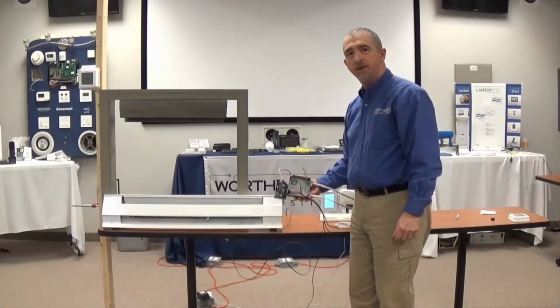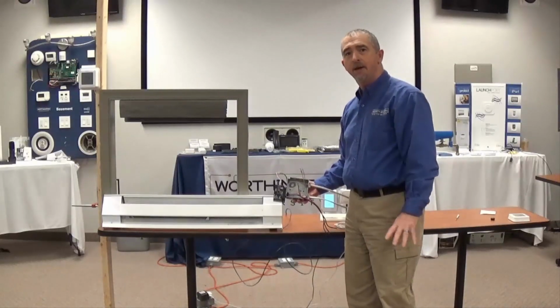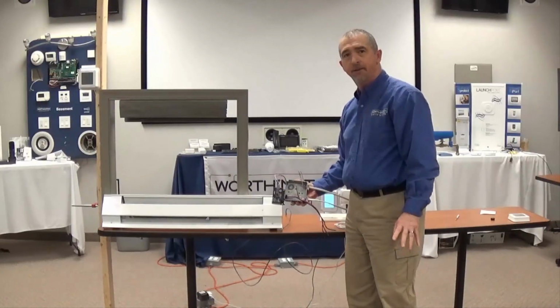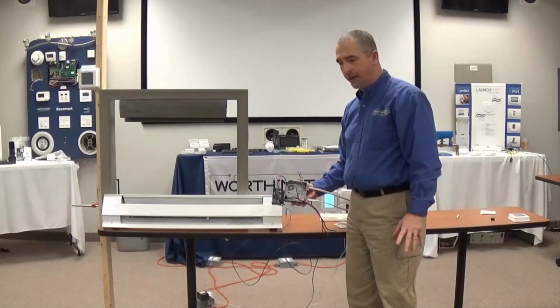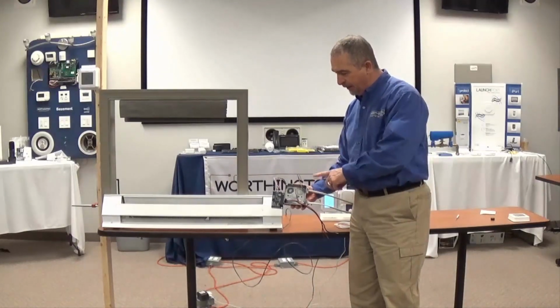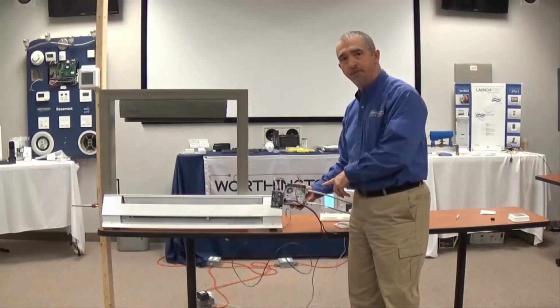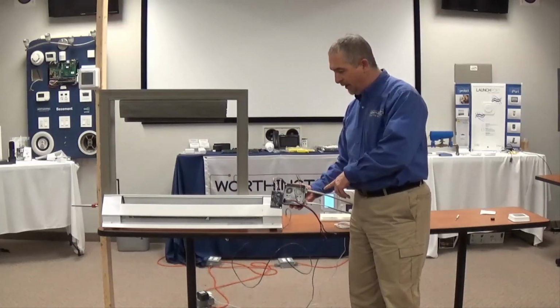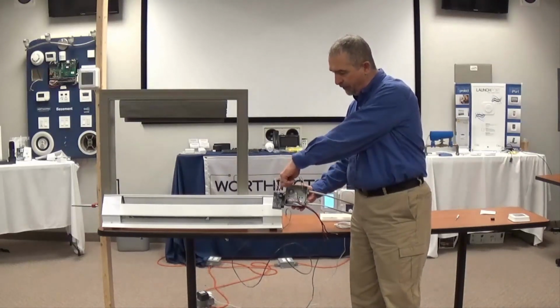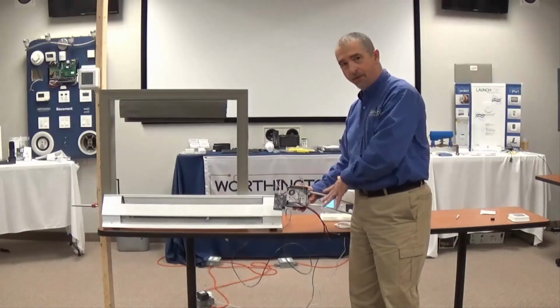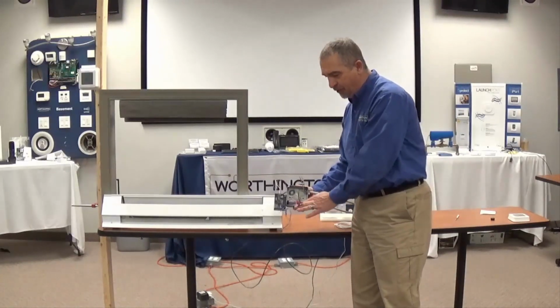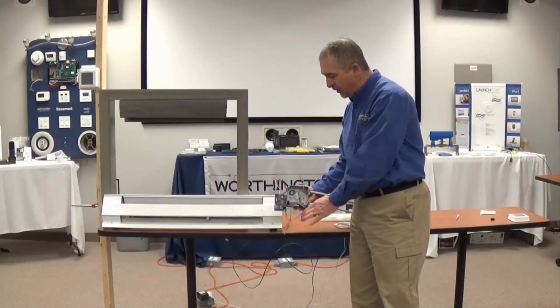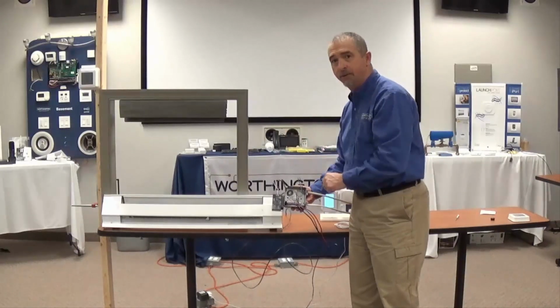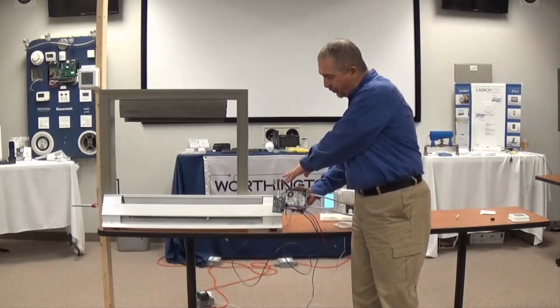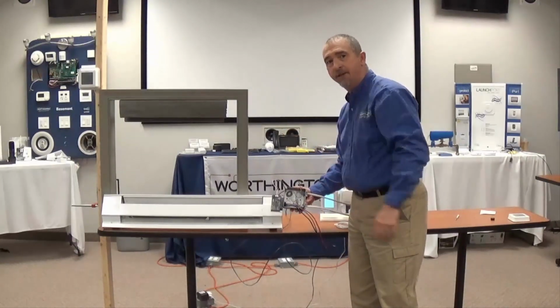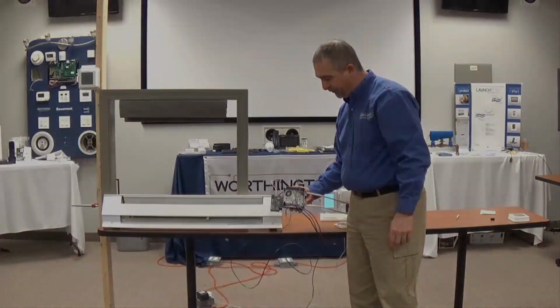In this section, I want to show a third option for how you can tie the low voltage thermostat into the 220 volt system. Here, there was a splice box in the basement, and all I did was install the module into the splice box—of course, power is off. Then I just need to do the line voltage wiring here to control the baseboard heaters upstairs, and I run the low voltage thermostat to any convenient place within the living space.